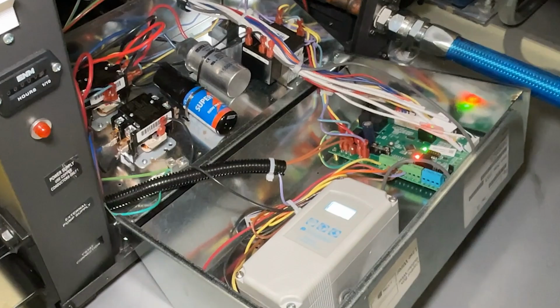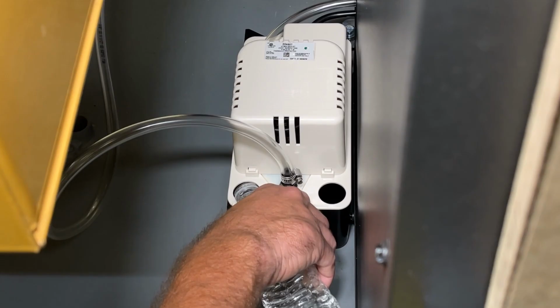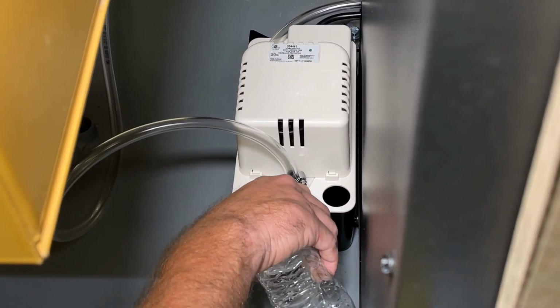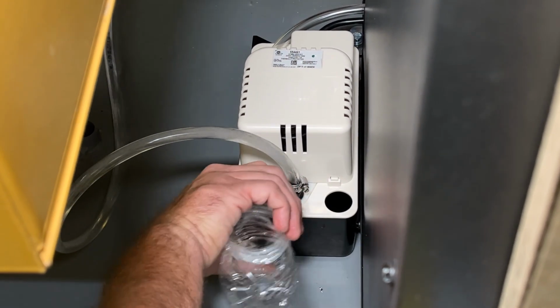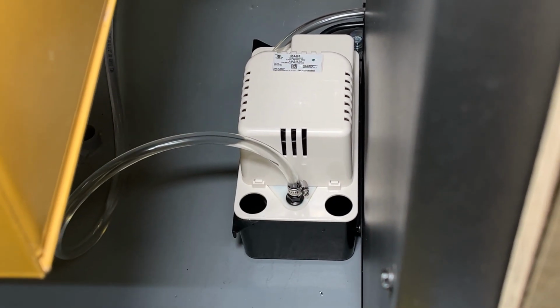Power can be wired directly into the HE electrical panel for a 208 or 240 volt powered condensate pump. See electrical schematics located in the operation manual for connection location. When power is available, prime the pump with water to confirm operation. Use heat trace and/or insulation on the condensate line or pump if either are potentially exposed to freezing conditions.